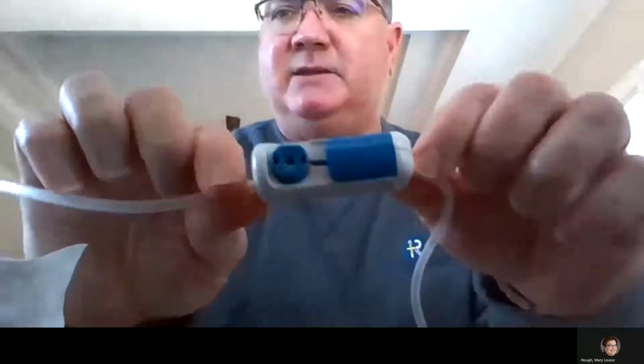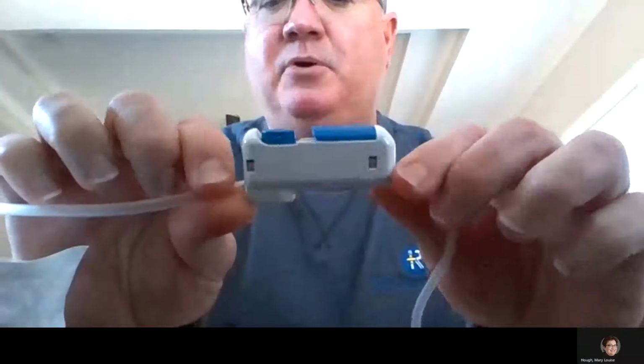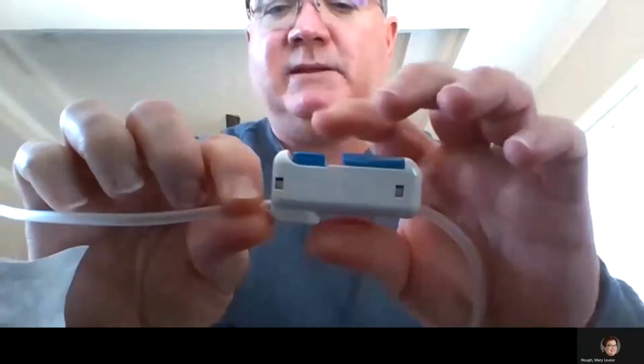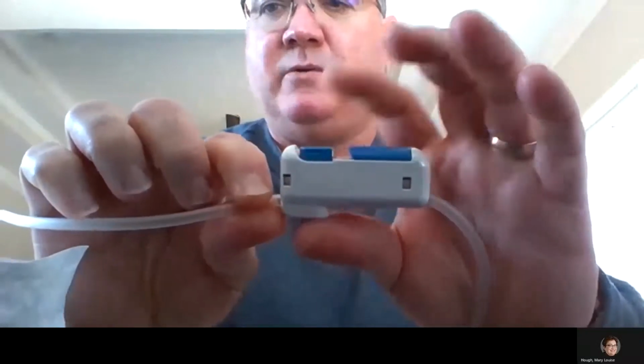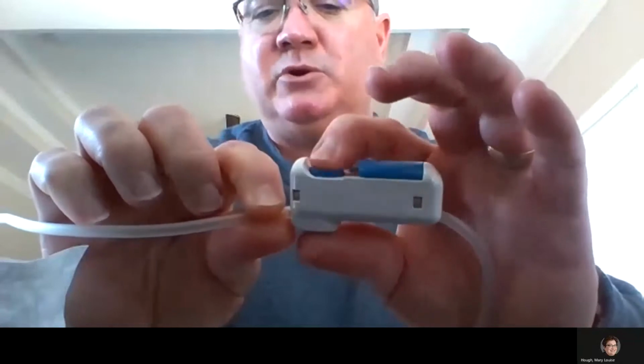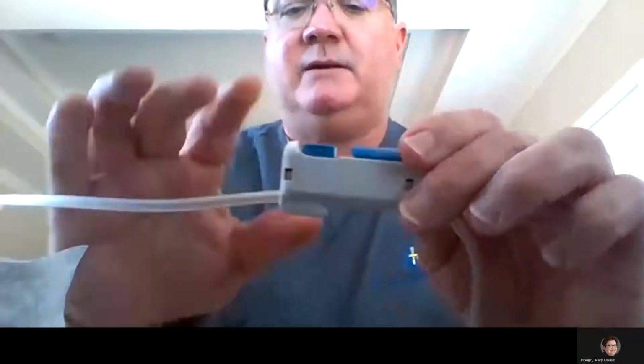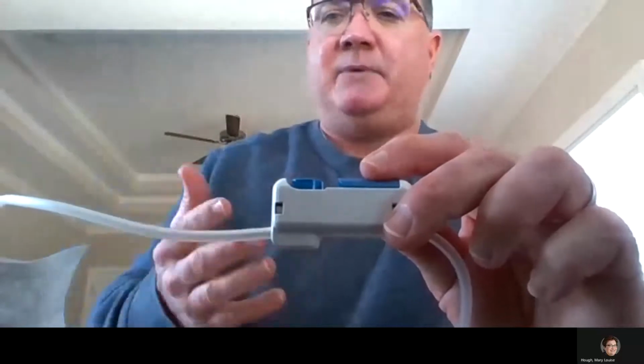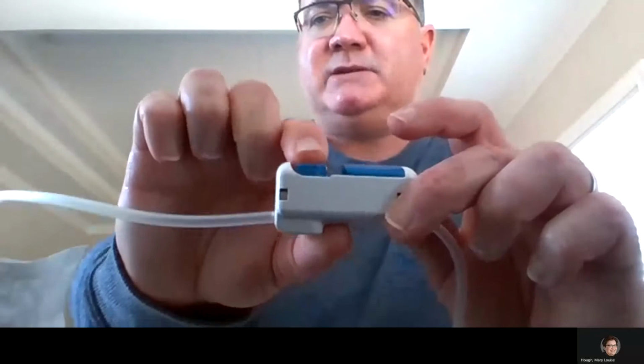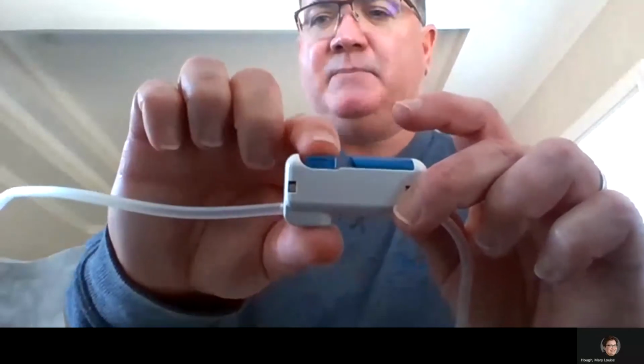In the middle is what actually activates the drain itself. This is a total push button control. So this allows the user, the patient or the nurse, to introduce the patient to drainage, so they're not shocked, because the initial shock can be very jolting sometimes, especially what they're used to with the Pleur-evac bottle. So once you start that drain, you can't stop it. It's a roller clamp and it's very hard to manage.